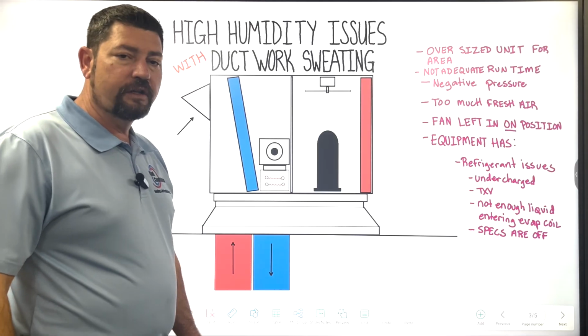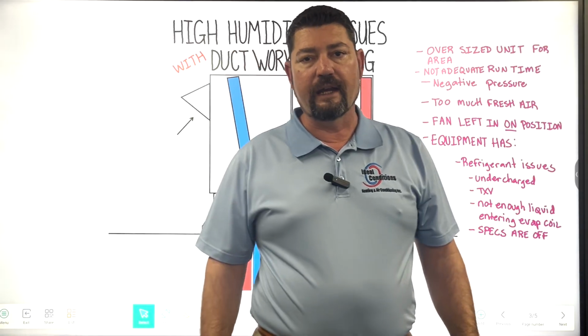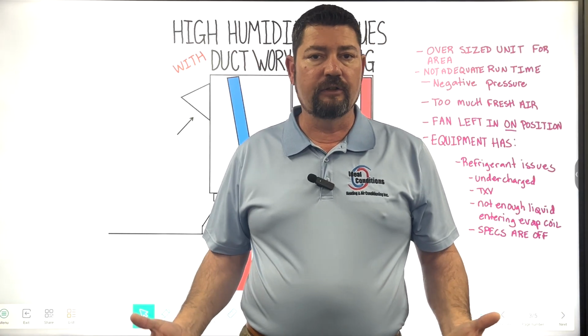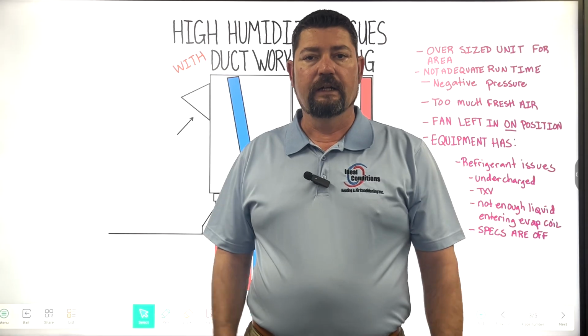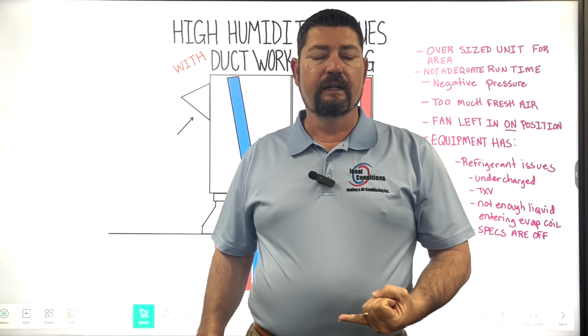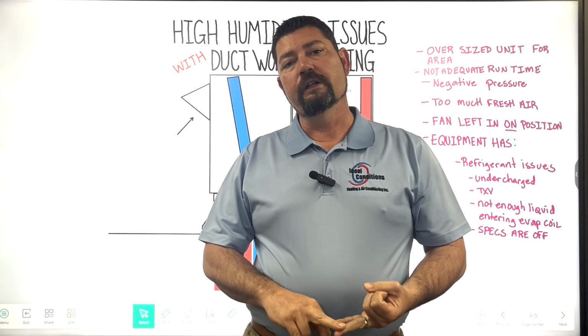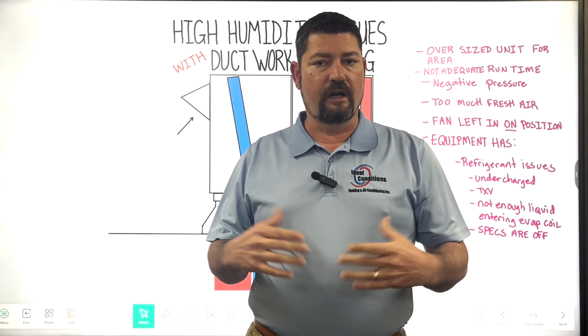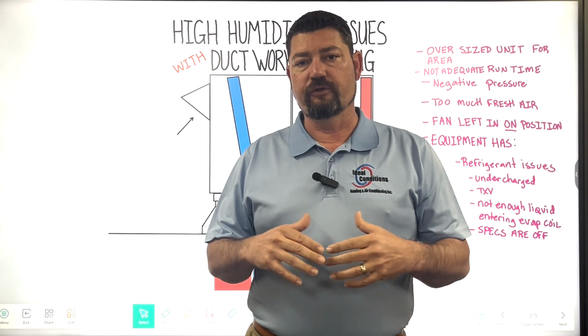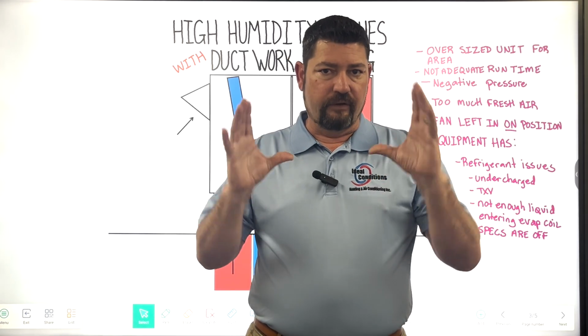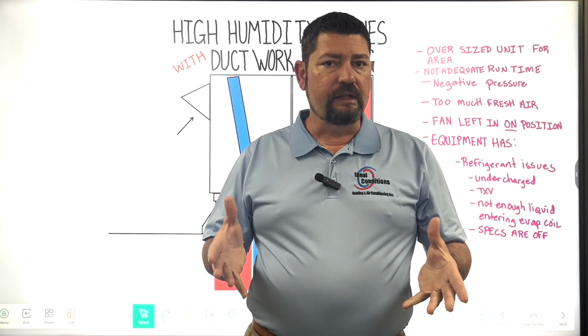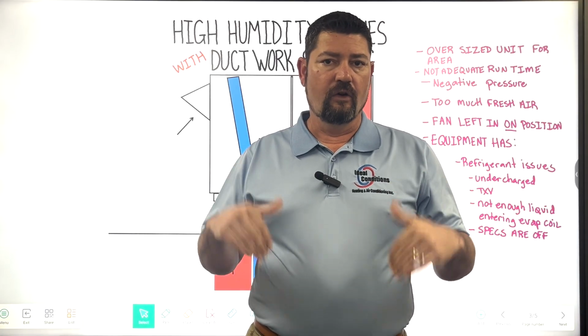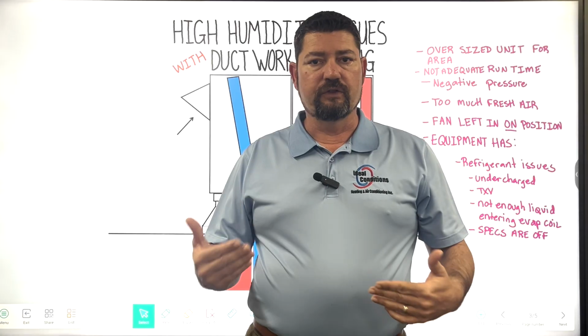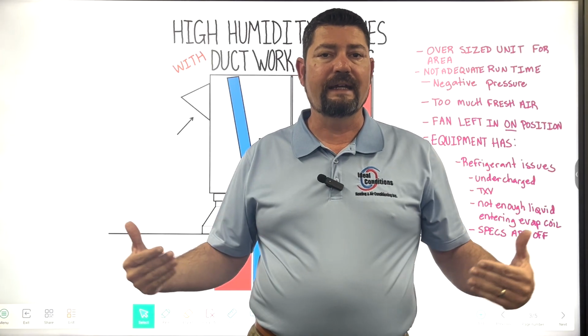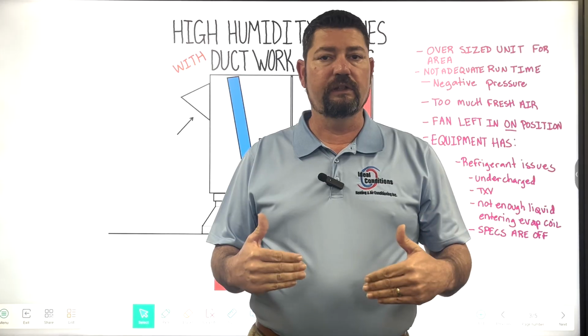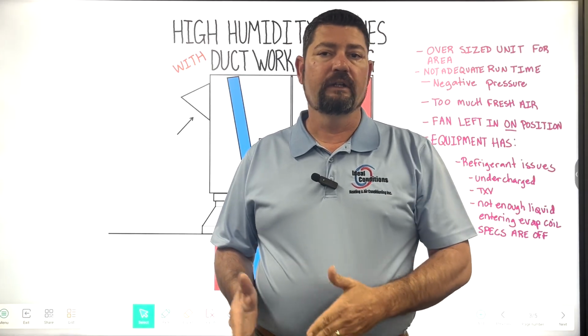In today's video, we're going to go over high humidity concerns involving package units on the roof, commercial application, whether it's single phase or three phase. We're going to go over common problems where water gets into the building from the package unit, what you can do about that, what you need to look for since this is a common occurrence. Additionally, when your ducts are sweating, we're talking about the outside of the ducts and that water is dripping down on ceiling tile or that water is dripping from the vents onto the floor. If it's a restaurant situation, anything that may invite humidity in that would collect on those surfaces and what you need to do about it and where to look. So stay tuned.